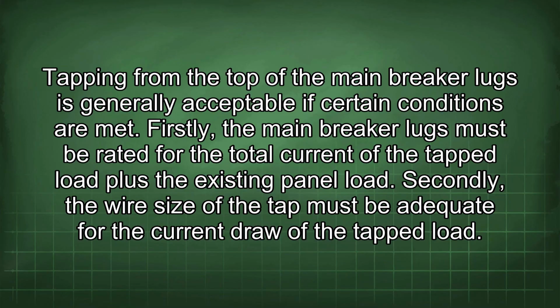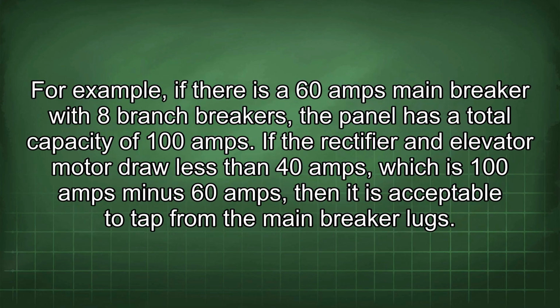Tapping from the top of the main breaker lugs is generally acceptable if certain conditions are met. Firstly, the main breaker lugs must be rated for the total current of the tapped load plus the existing panel load. Secondly, the wire size of the tap must be adequate for the current draw of the tapped load. For example, if there is a 60 amp main breaker with 8 branch breakers, the panel has a total capacity of 100 amps. If the rectifier and elevator motor draw less than 40 amps, which is 100 amps minus 60 amps, then it is acceptable to tap from the main breaker lugs.